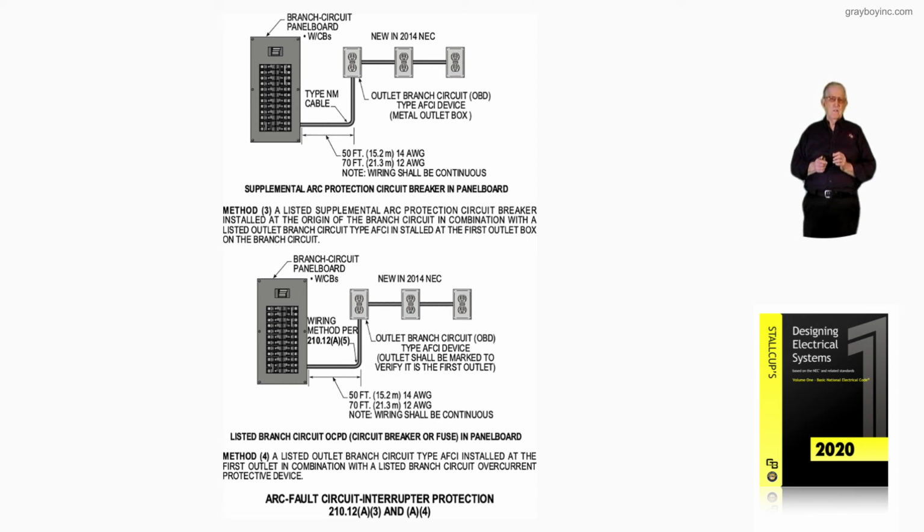I notice that a lot of your contractors are just still using the circuit breaker. That is a combination type circuit breaker that has ground fault, short circuit, overload, and AFCI. Some of them are even buying one that has a GFCI also. And they'll put those in there for these circuits, because now all outlets have to be protected by AFCI in a dwelling unit. And notice it does say outlet.